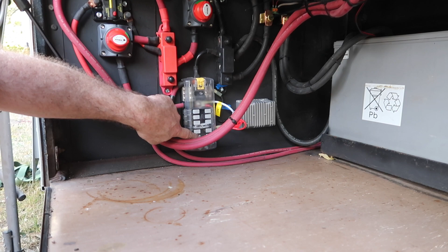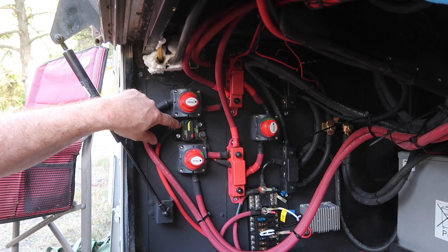Let's talk about this brick for a minute. So we have a split bus power bus panel here. On this side we have 12 volts, and on this side, the B side, we have 24 volts, and these are just standard ATO fuses in here. I just put some extra fuses in there, but really we have this 125 amp fuse here. Then we have your shared ground, and this is your 12 or your 24 volt side down here. So we have a 30 amp breaker protecting everything on the 24 volt side, and then we have a couple of cables here that come from the 12 volt side.